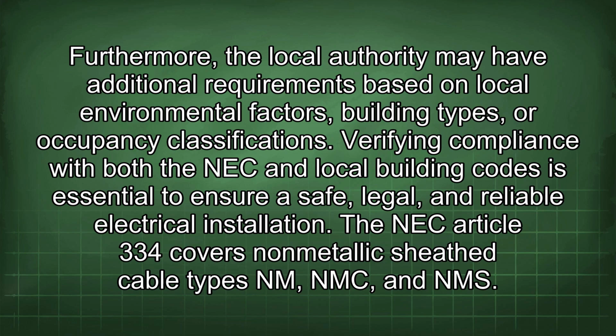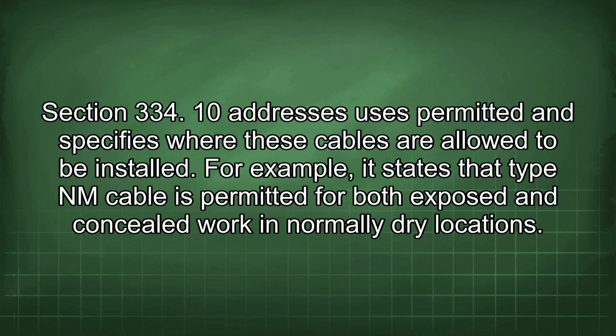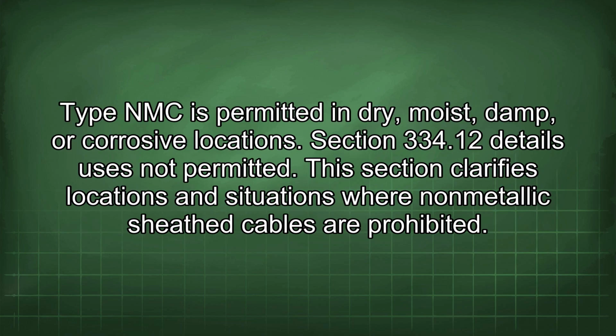The NEC Article 334 covers non-metallic sheathed cable types NM, NMC, and NMS. Section 334.10 addresses uses permitted and specifies where these cables are allowed to be installed. For example, it states that type NM cable is permitted for both exposed and concealed work in normally dry locations. Type NMC is permitted in dry, moist, damp, or corrosive locations.